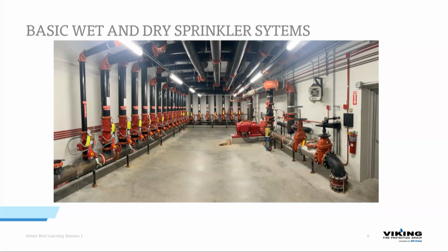That's coming in from our loop, whatever it is, our water tank. This is the water supply coming into the pump house room, the pump room. Backflow prevention device with two OS&Ys. They're both going to have tamper switches on them, so you can't shut these off without an alarm going off. This next run of pipe takes you to your fire pump and your jockey pump.